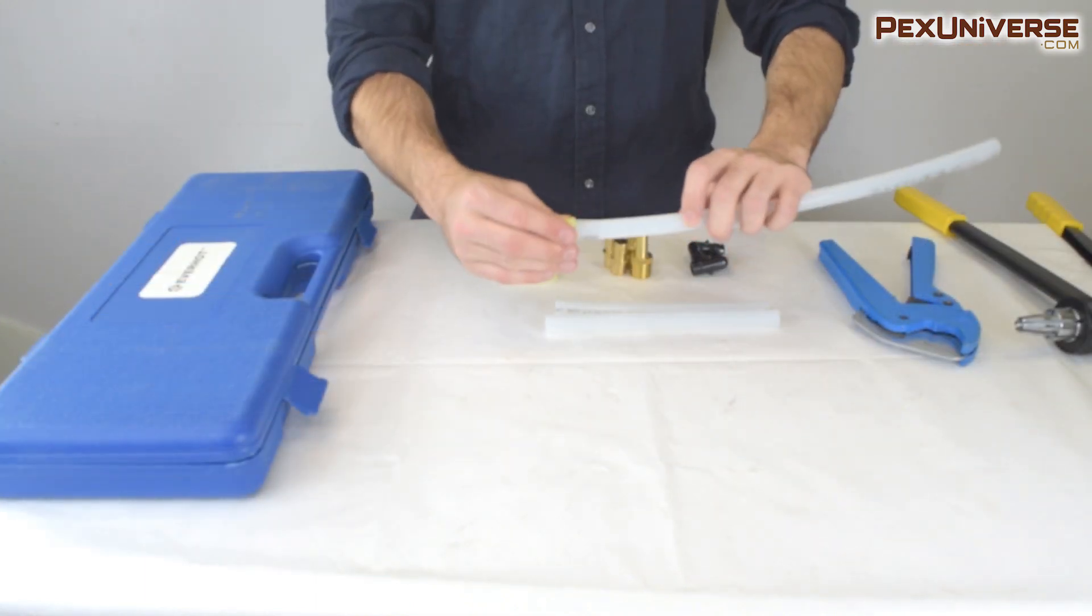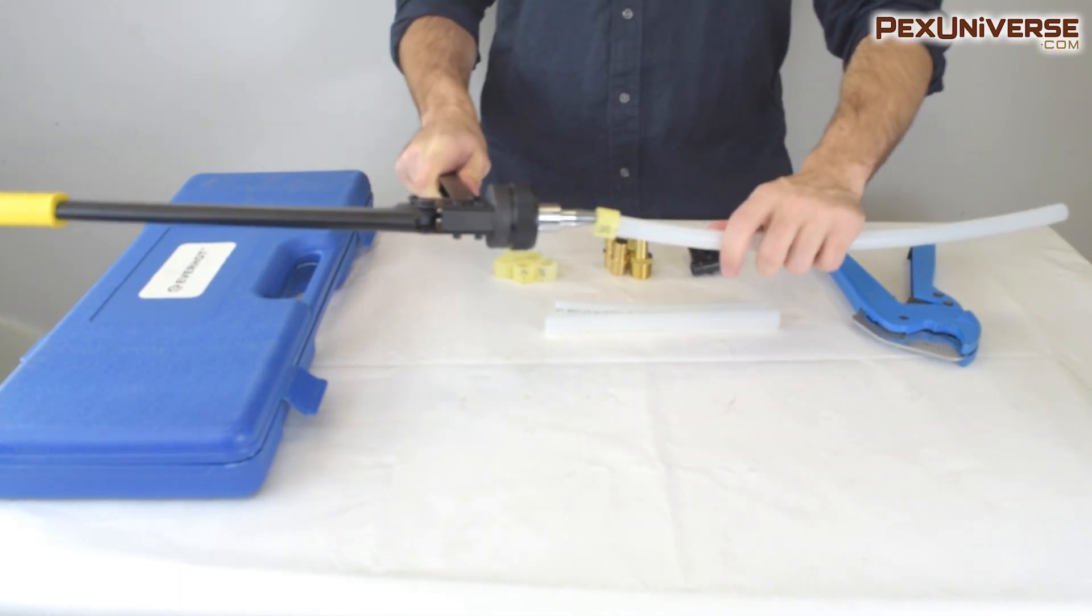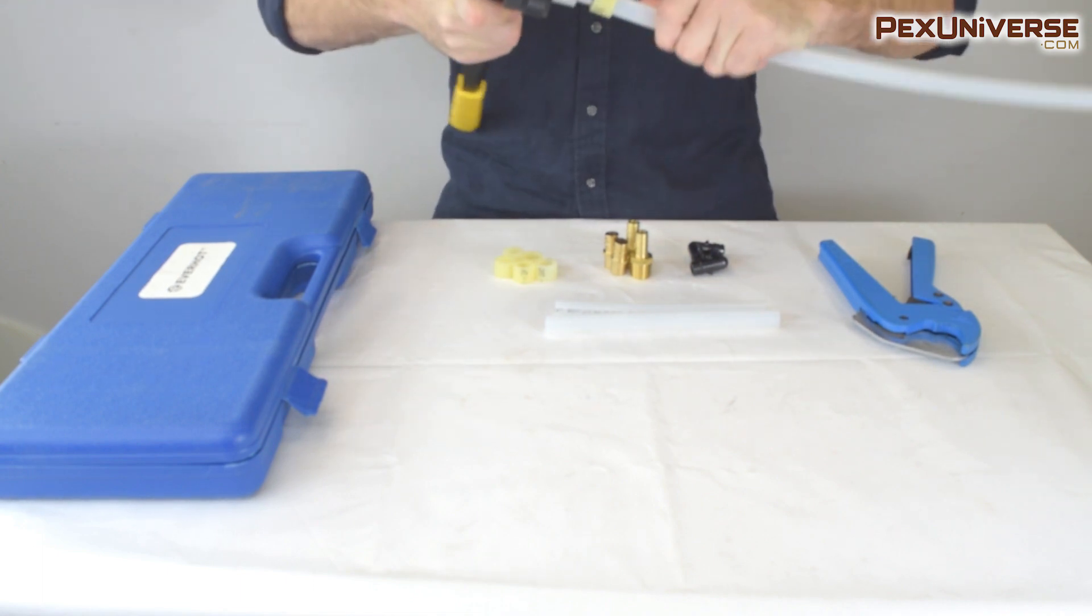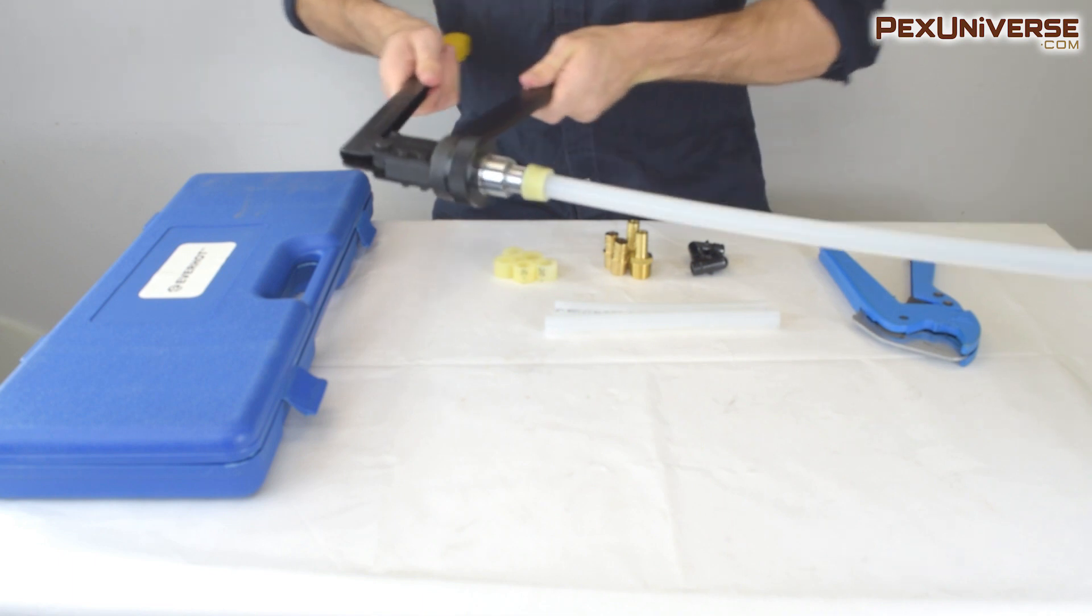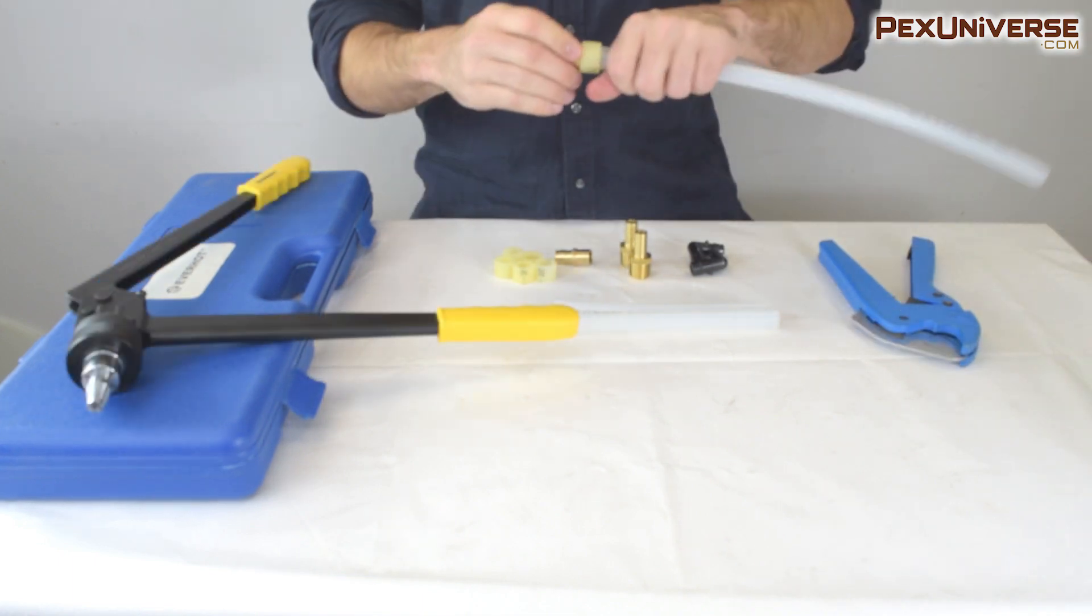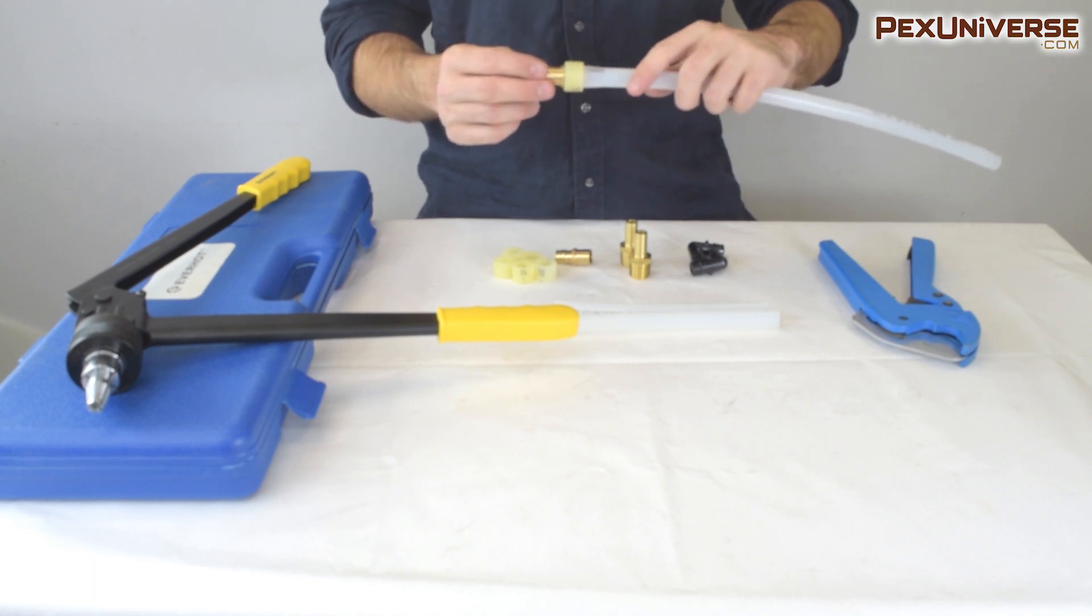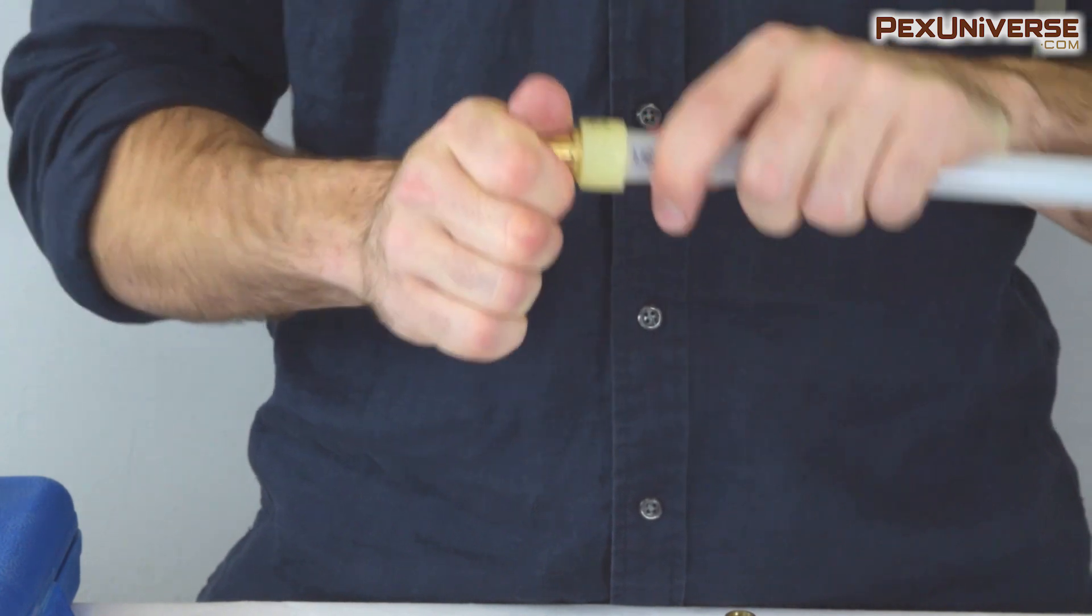You take your expander ring and place it over the tubing. This is half inch tubing so I have a half inch ring. Make sure you get the right head size of the tool and insert it. Expand it a few times until it's open and then insert the fitting. All you have to do after that is wait until the tubing fixes itself and secures the fitting.